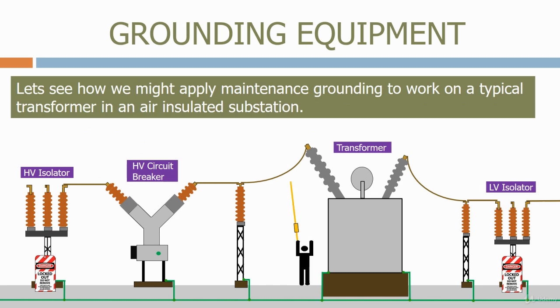The electrical operator uses an electrical tester to make sure that the high voltage conductors are indeed dead. He repeats this procedure on the low voltage conductors. A ground lead is now attached to the nearest ground spigot. This is directly connected to the substation ground grid.